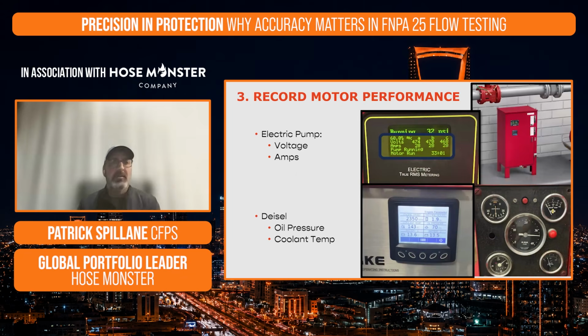And then the last piece of data that we need to record is going to be our motor performance. So if this is an electrical fire pump, we need to record the voltage and amperage at each phase, right, throughout the test at each flow point. Or if it's a diesel engine, we want to record the oil pressure and the coolant temperature. So there is no amps and volts to record with diesels. But we want to make sure that the oil pressure is stable and our coolant temperature is within normal conditions. The temperature range may vary per manufacturer of that diesel engine, but typically we're looking at around 180 degrees Fahrenheit. And I apologize, I don't know what that is in Celsius, but I'm sure we could do some math there to figure that out. But again, you want to consult your manufacturer's recommendations on the proper temperature rating for that fire pump.